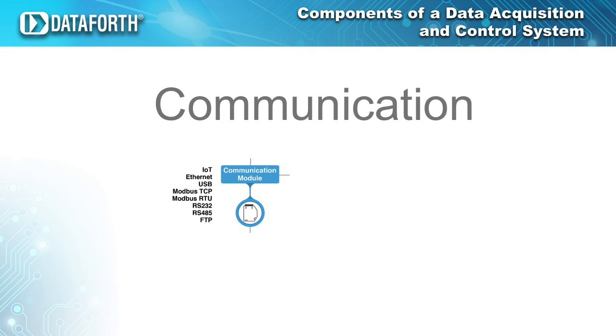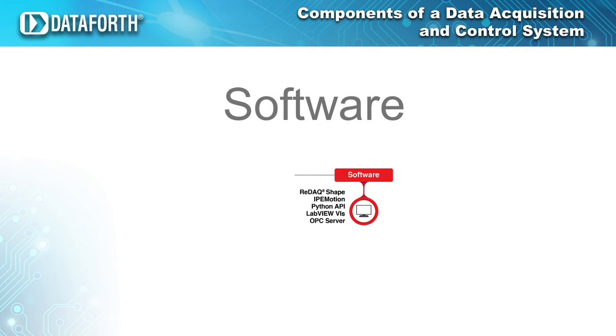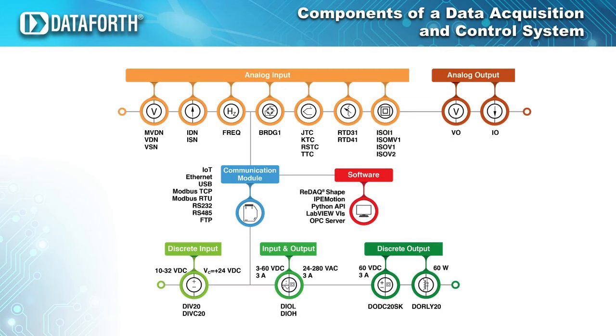Many of today's data acquisition systems support different communication methods, such as, but not limited to, USB or Ethernet communication, and support communication protocols such as, but not limited to, TCP/IP, FTP transfer, or Modbus TCP. But without software, your hardware is meaningless. So, in general, everyone who sells data acquisition systems provides some sort of software. However, good data acquisition system manufacturers are designing their systems to allow interfacing to a multitude of other software packages. This open architecture, sometimes supported with APIs such as the Python API, which is more modern, allows the use of already installed and familiar software, whether it is proprietary or off the shelf. Putting all the individual pieces together, here's a quick look at what a modern data acquisition and control system looks like.